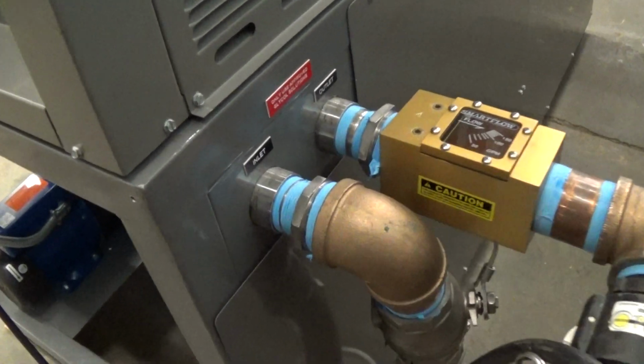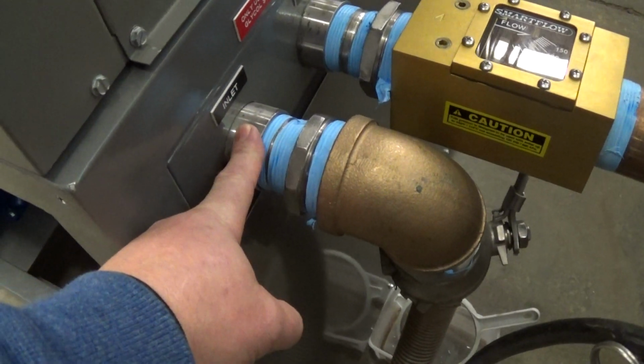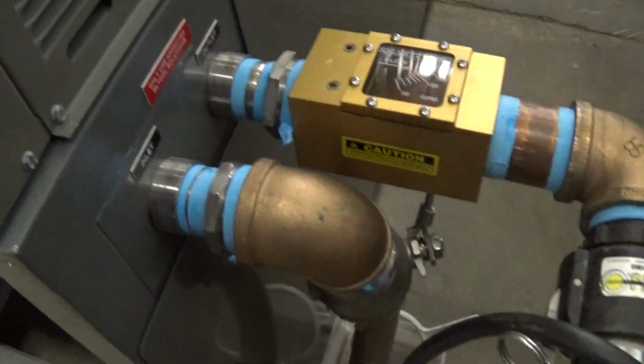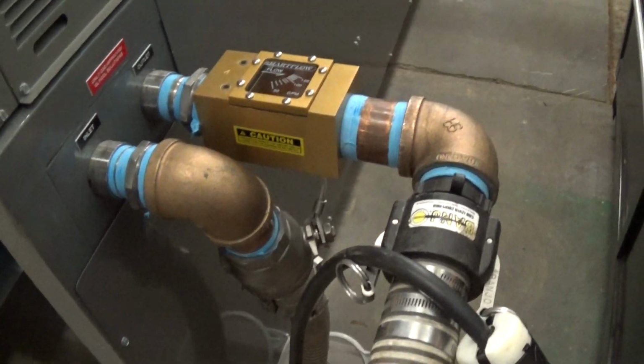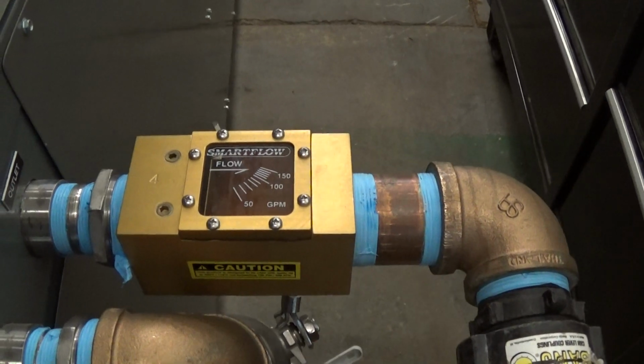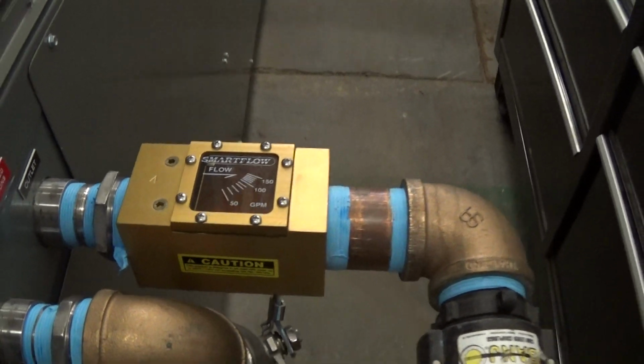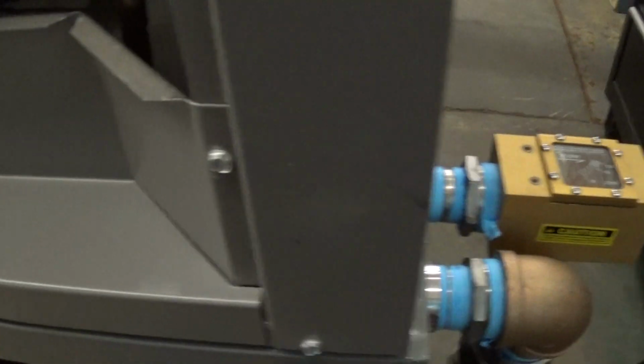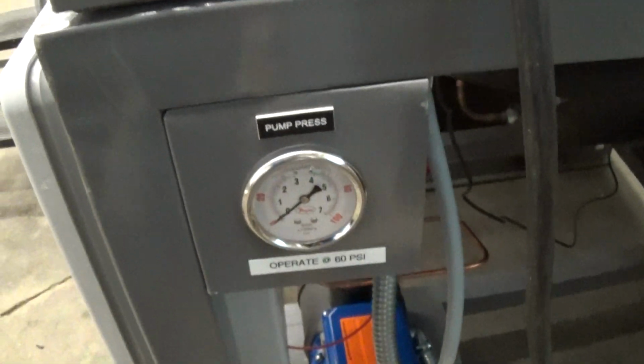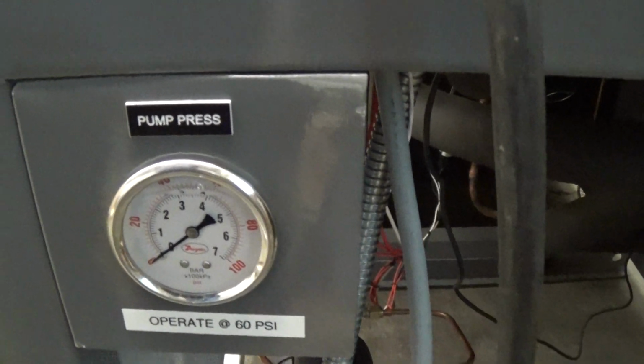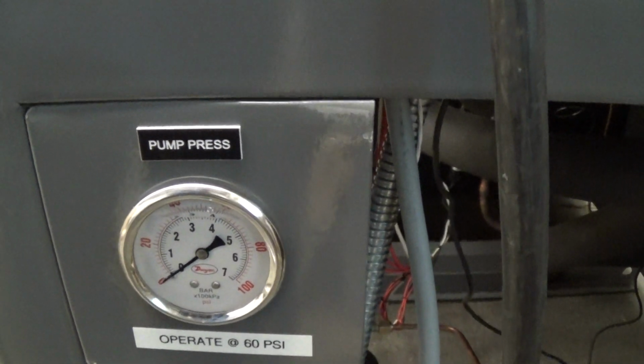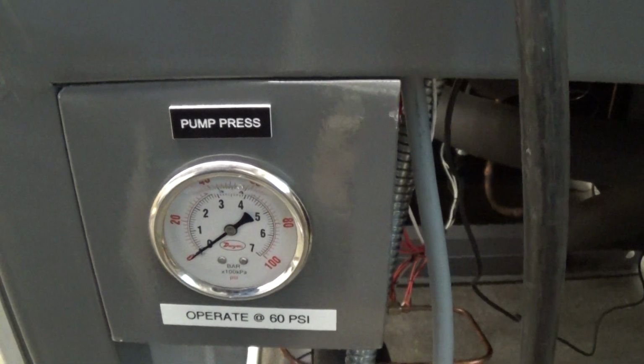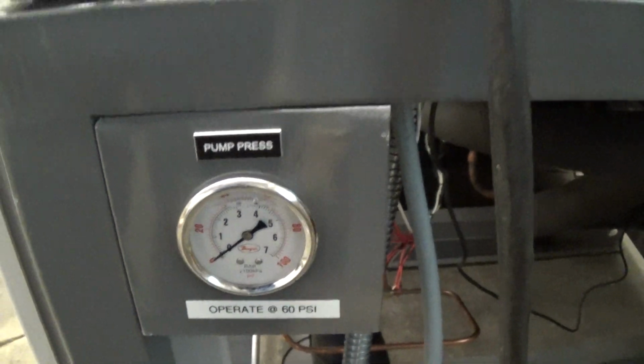The 10-ton unit comes with these 1.5-inch NPT fittings here. For our test runs, we put on a loop, and we actually put on a GPM flow meter to measure what type of flow we got. In this case here, because we upgraded the pump on this particular unit, we also upgraded the pressure gauge to a higher pressure gauge. This pump can do about 60 psi at 30 GPM.